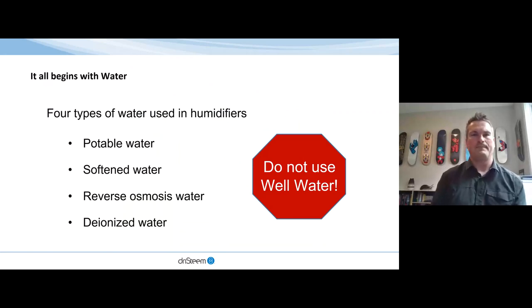But whether we look at isothermal or adiabatic, humidification all begins with water. And so what is in the water and the constituents that make up that water is really important to the longevity, the maintenance, the life of the system, and the performance of that system. So the 4 types of water that you can use are potable water, softened water, reverse osmosis water, and deionized water. We do not recommend using well water. There's too many constituents and too many other types of variables involved with well water and inconsistencies. And so we do not recommend the application of well water.